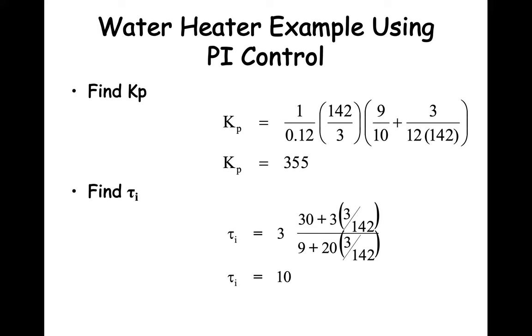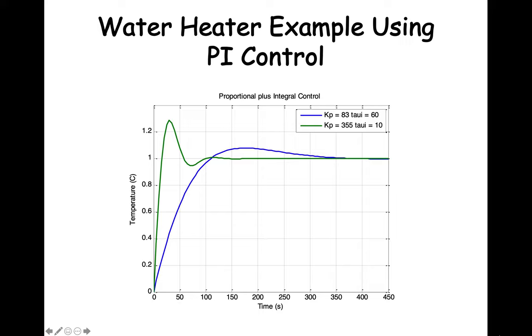Assuming proportional plus integral control, we use the equations shown to find Kp and tau i. In this case, Kp equals 355 and tau i equals 10. These are quite different from the numbers we used before. Here is a graph of the two responses using PI control and the unit step change. The blue line is the result using Kp equals 83 and tau i equals 60 — we don't get much overshoot, but it takes much longer to get within 5% of the final value, which is over 300 seconds. The green line is the response using Kp equals 355 and tau i equals 10. We have approximately 25% overshoot, which is acceptable for good control, and the response settles down to within 5% of the final value much faster, around 100 seconds.